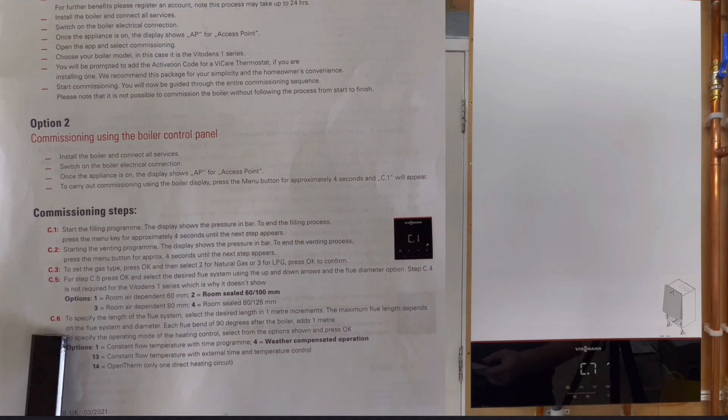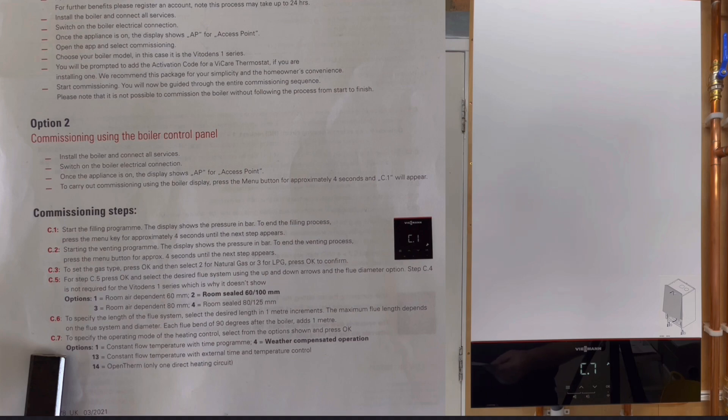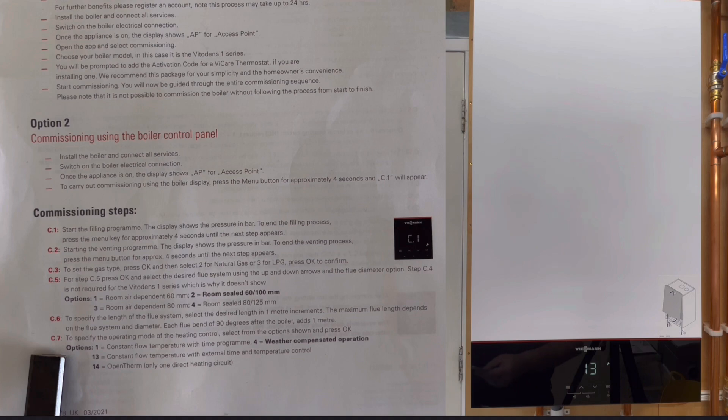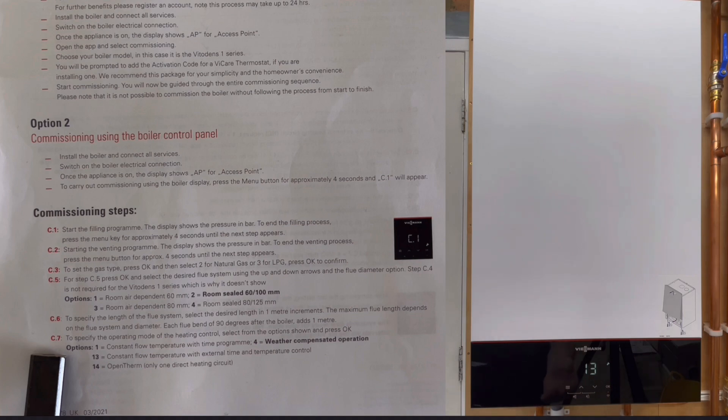We click OK and that takes us to C7. On C7 this then tells us what we've got the boiler set as. We've got it set as 13, which is constant flow temperature with an external time and temperature control. This is just your normal room thermostat. We've got this particular system on an S plan at the moment, so that's why it's at 13.